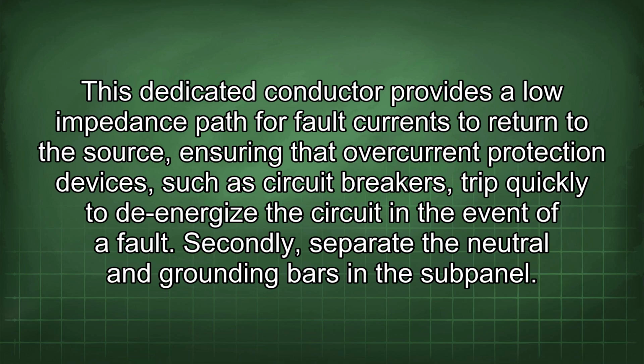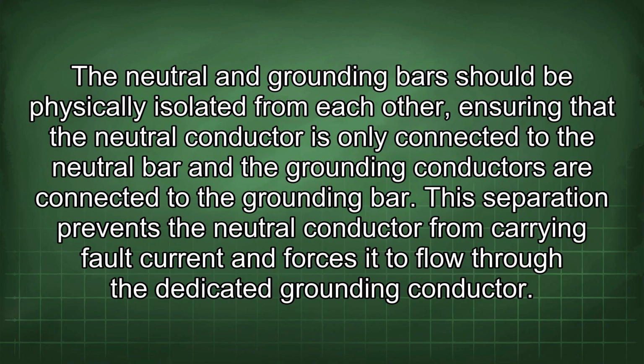Secondly, separate the neutral and grounding bars in the subpanel. The neutral and grounding bars should be physically isolated from each other, ensuring that the neutral conductor is only connected to the neutral bar and the grounding conductors are connected to the grounding bar. This separation prevents the neutral conductor from carrying fault current and forces it to flow through the dedicated grounding conductor.